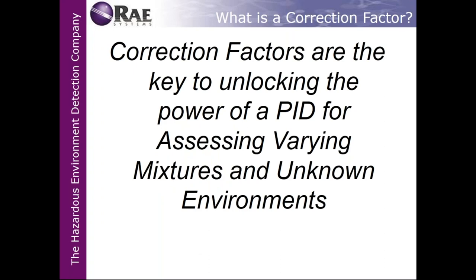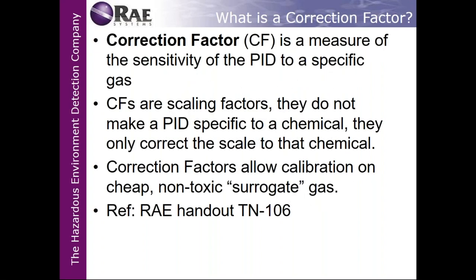Again, what is a correction factor? The correction factors are the key to unlocking the power of the PID for assessing varying mixtures and unknown environments. The correction factor is a measure of the sensitivity of the PID to a specific gas. Correction factors are scaling factors that do not make a PID specific to a chemical. They only correct the scale to that chemical. So as I mentioned before, correction factors are based on the table of isobutylene, which is 1.0.